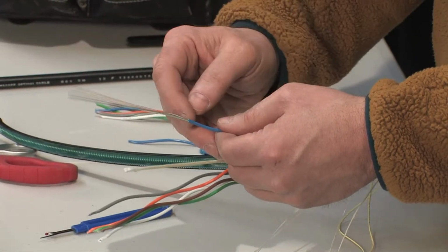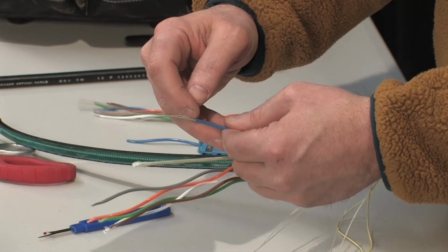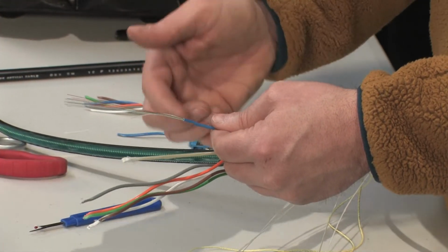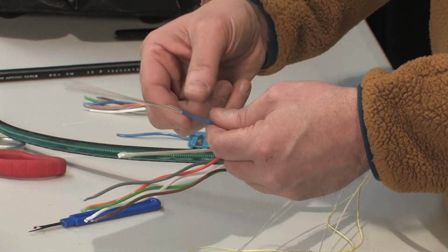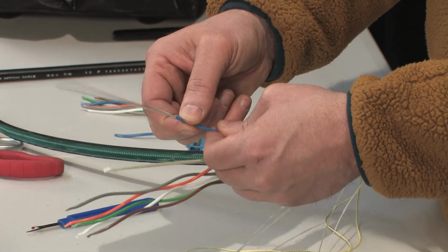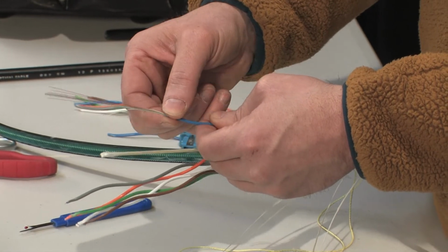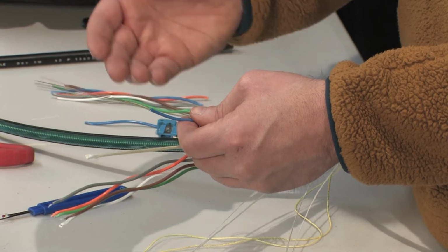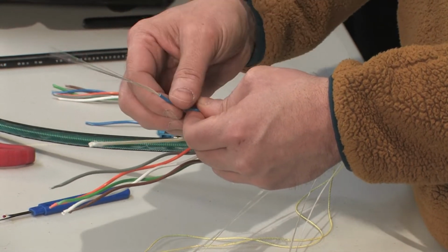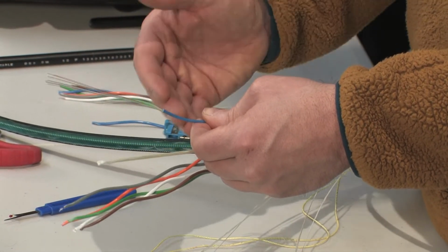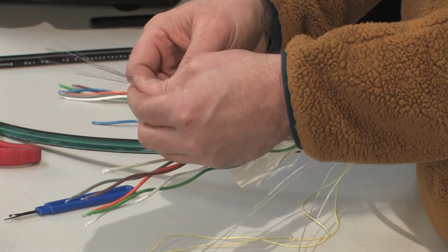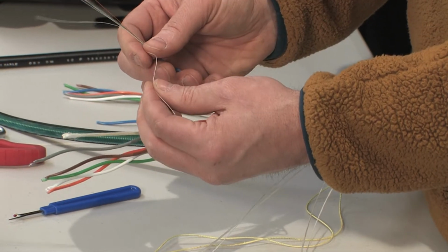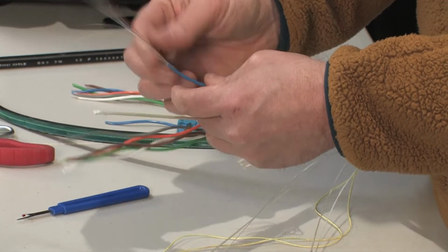Well, if the water is inside the case, then there's the high likelihood that the water can wick inside of here due to the temperatures heating and cooling. It'll eventually draw into this like a straw. If that has the ability to freeze inside of there, it has the potential to snap the fibers in two. Again, for inspection purposes, if that had froze and broke those fibers, it would take us a long time to find that problem. So once these two strands get wet, they turn to a gel, and it no longer has the capability to freeze.